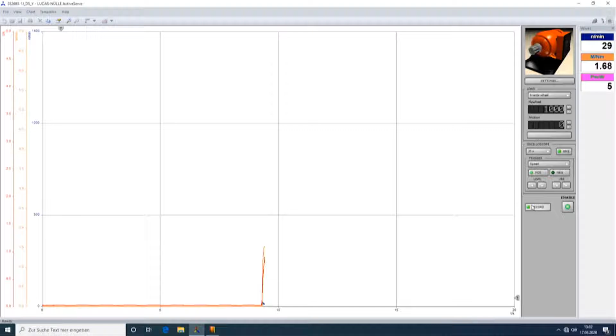Start enable again, and press record button. What we see here is now all the values are measured. And now I can start in the next step the motor. If I start the motor in the Y, see what happens, and then I switch to delta, I can see directly the behavior.